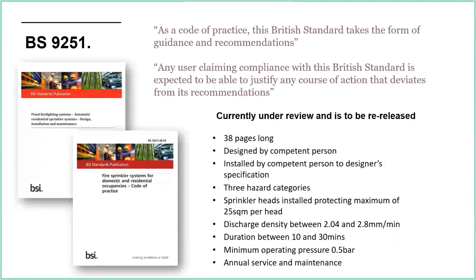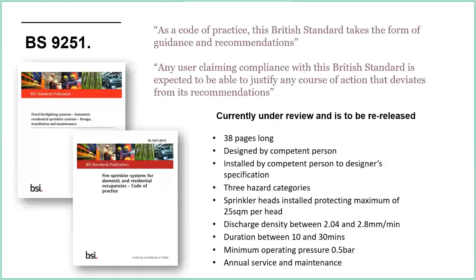Duration is between 10 and 30 minutes: category one is 10 minutes, categories two and three are 30 minutes — that's the minimum duration for sprinklers to operate based on the worst case scenario. Minimum operating pressure is half a bar, and annual service and maintenance is required.